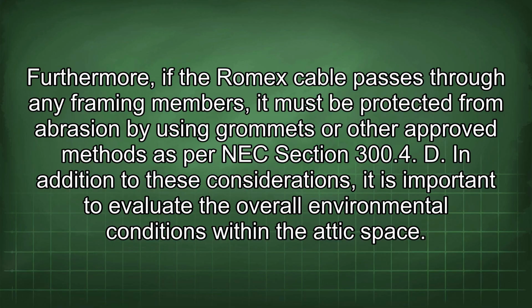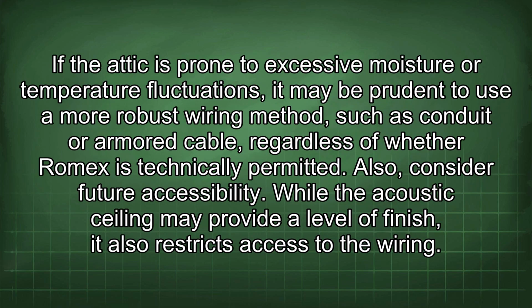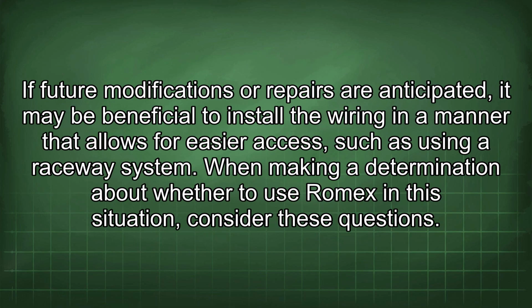In addition to these considerations, it is important to evaluate the overall environmental conditions within the attic space. If the attic is prone to excessive moisture or temperature fluctuations, it may be prudent to use a more robust wiring method, such as conduit or armored cable, regardless of whether Romex is technically permitted. Also, consider future accessibility. While the acoustic ceiling may provide a level of finish, it also restricts access to the wiring. If future modifications or repairs are anticipated, it may be beneficial to install the wiring in a manner that allows for easier access, such as using a raceway system.